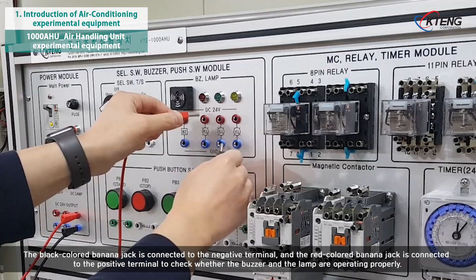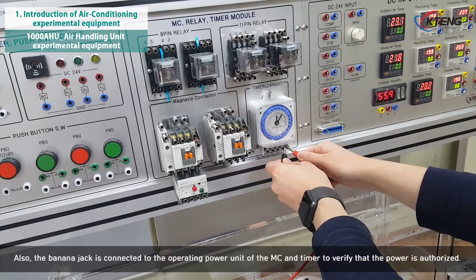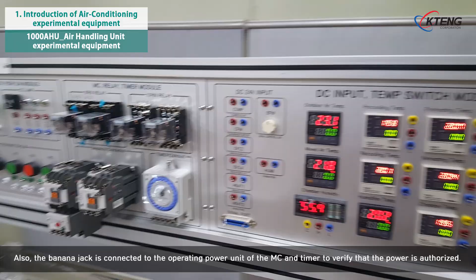The positive terminal is connected to number 2 terminal and negative terminal to the number 7 terminal of the 8-pin relay, and the relay is checked for being energized. For the 11-pin relay, the positive terminal is connected to the number 10 terminal, and the negative terminal to the number 2 terminal for checking the proper operation. Also, the banana jack is connected to the operating power unit of the MC and timer to verify that the power is authorized.